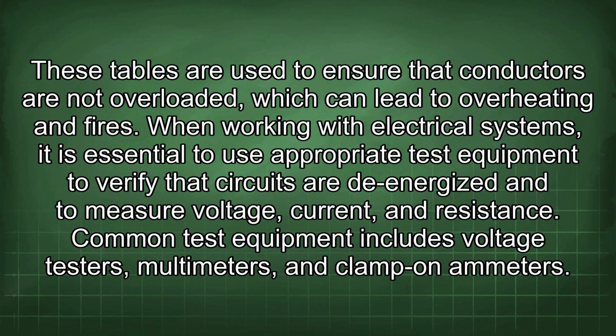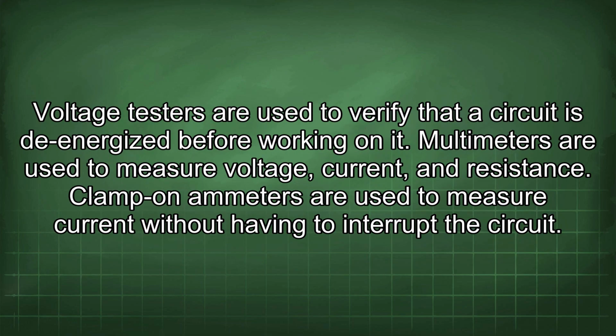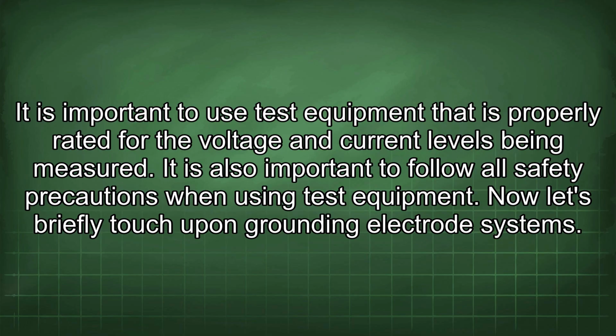When working with electrical systems, it is essential to use appropriate test equipment to verify that circuits are de-energized and to measure voltage, current, and resistance. Common test equipment includes voltage testers, multimeters, and clamp-on ammeters. Voltage testers are used to verify that a circuit is de-energized before working on it. Multimeters are used to measure voltage, current, and resistance. Clamp-on ammeters are used to measure current without having to interrupt the circuit. It is important to use test equipment that is properly rated for the voltage and current levels being measured. It is also important to follow all safety precautions when using test equipment.